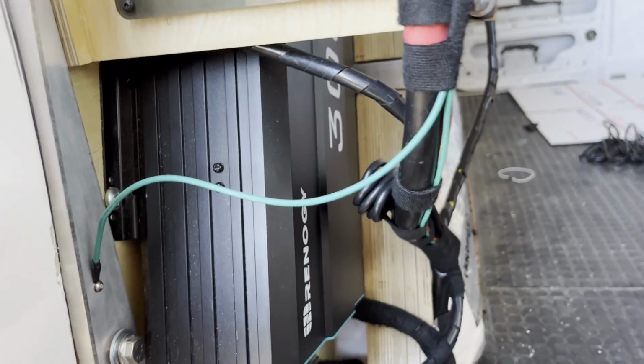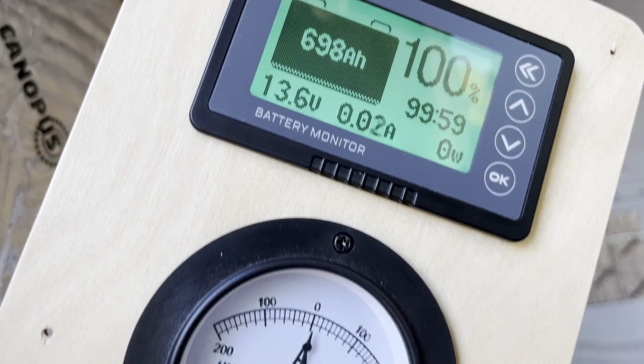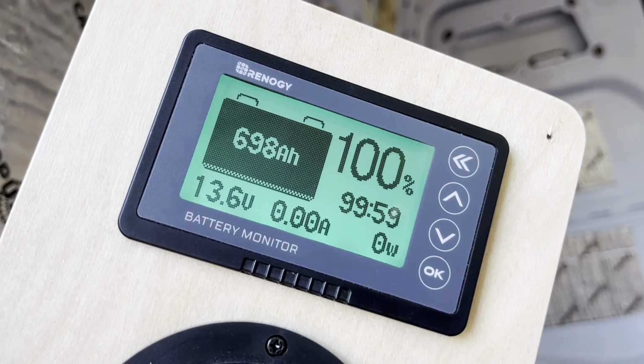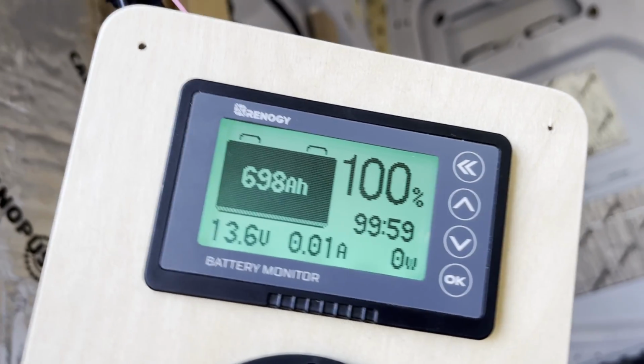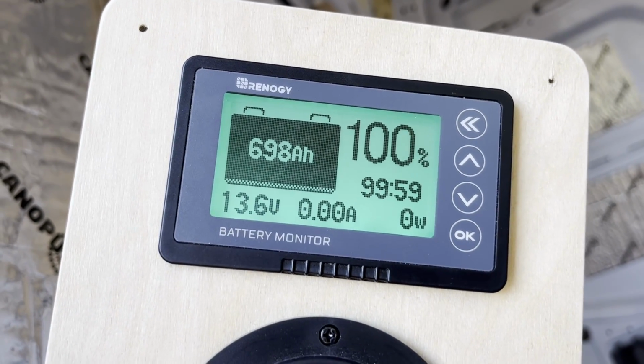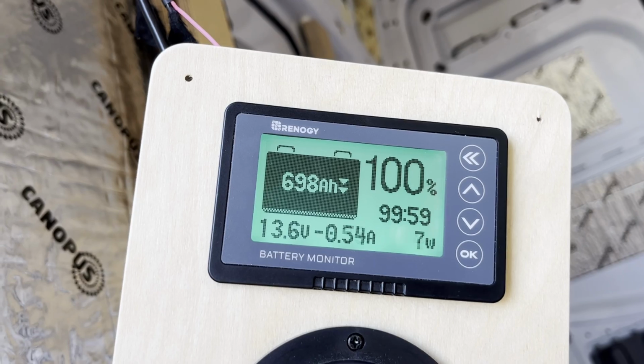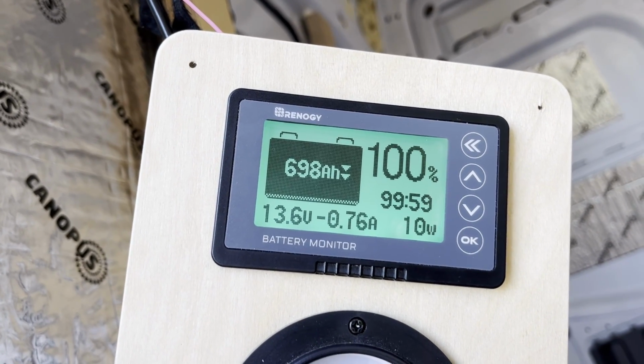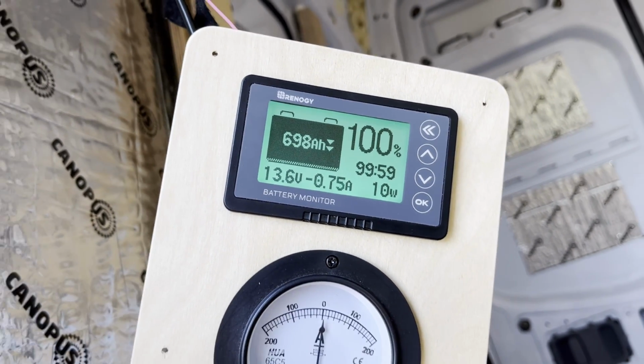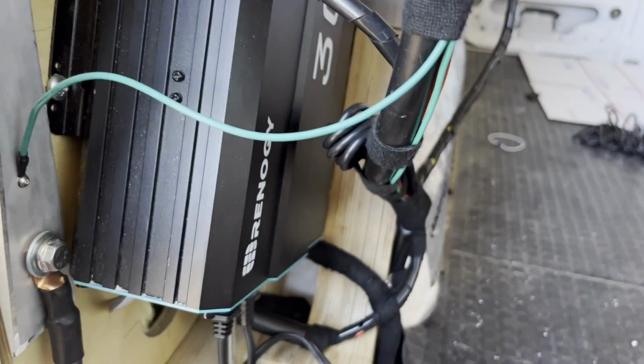So if I turn off the inverter, you'll see the amperage goes down to basically 0. Now let's go ahead and turn the inverter back on. It pulls up, and you can see that now the current draw is about 700 milliamps. That's just the standby current of the inverter.